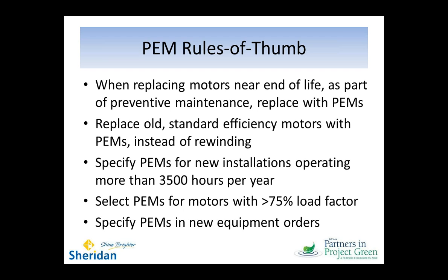Specify premium efficiency motors when you've got new installations going in, or anything that's operating more than 3,500 hours per year, because the economics are going to work in your favor. And likewise, if you're buying new equipment, specify premium efficiency motors. The manufacturers may substitute standard efficiency motors in, but you can ask them to get that replacement. Because of the standard frame sizes, it should be fairly easy for them to find a replacement to put in there straight away.